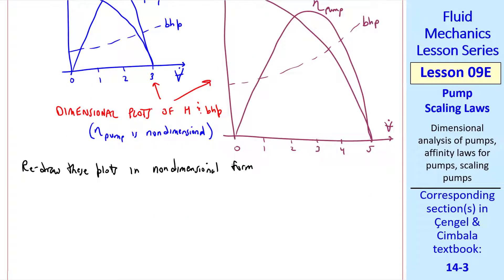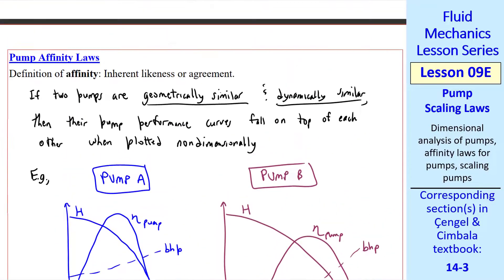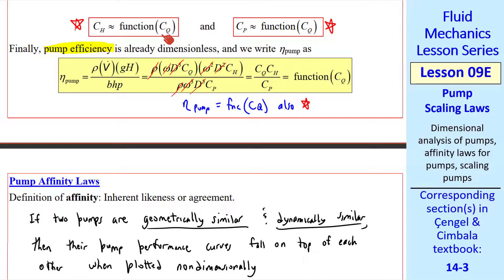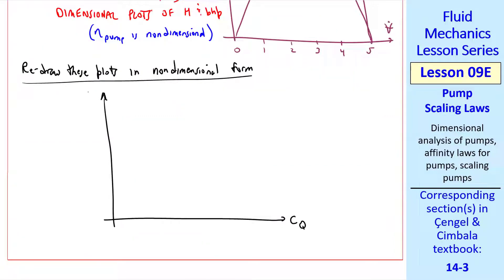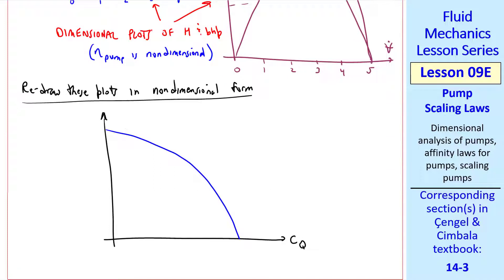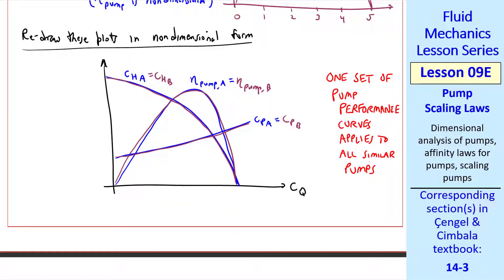Now let's redraw these plots in non-dimensional form. Going back to our equations, instead of head we'll plot CH. Instead of volume flow rate we'll plot CQ as our x-axis. And instead of BHP we'll plot CP. And then eta pump, of course, is also a function of CQ. So the non-dimensional plot will look something like this. Keeping our color code, pump A was blue, so this curve is CHA. Pump B was purple, so they fall on the same curve if we have dynamic similarity. Similarly, eta pump A equals eta pump B, and CPA equals CPB. The bottom line is that one set of pump performance curves applies to all similar pumps.